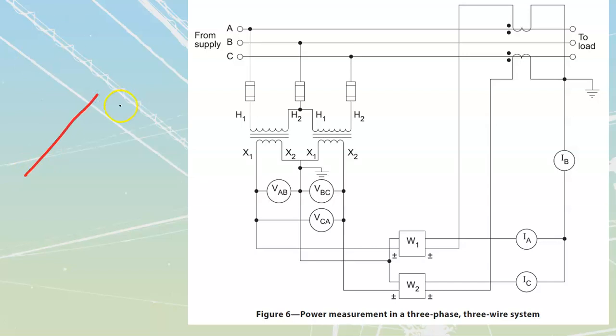A to B, B to C, C to A. So going from my A to B phase of the actual system, I see that I've got a voltmeter section placed across it, made up of an actual VT or PT, whichever you want to call it. I'm tapping off on line A, then going over to that voltmeter high voltage section, then across to line B. And I see that on A I've got my H1 section attached to it.